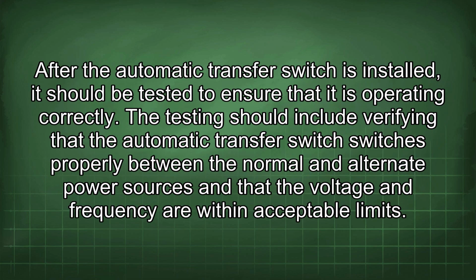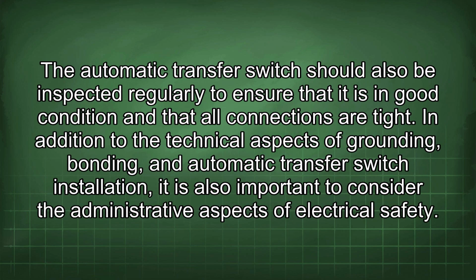After the automatic transfer switch is installed, it should be tested to ensure that it is operating correctly. The testing should include verifying that the automatic transfer switch switches properly between the normal and alternate power sources and that the voltage and frequency are within acceptable limits. The automatic transfer switch should also be inspected regularly to ensure that it is in good condition and that all connections are tight.